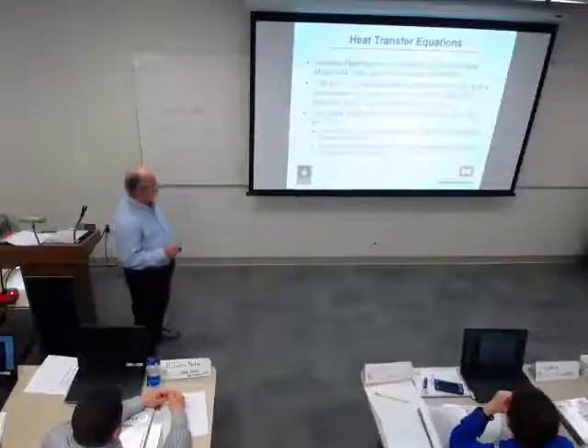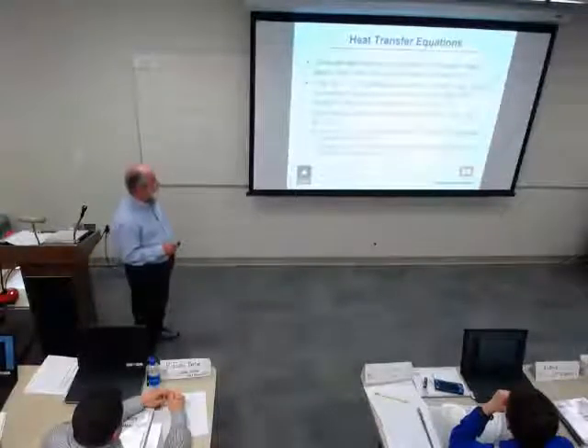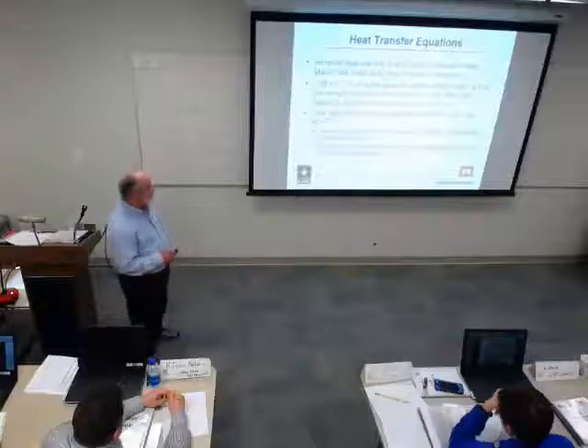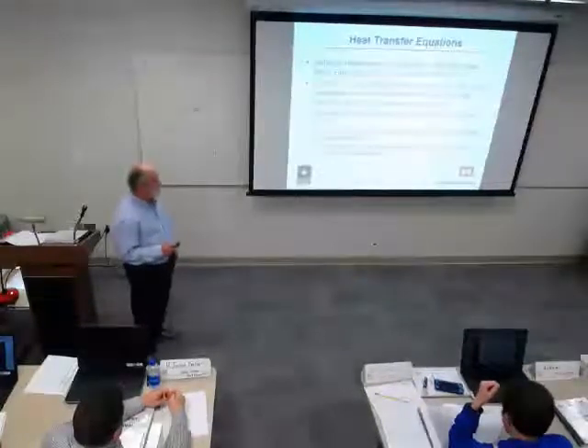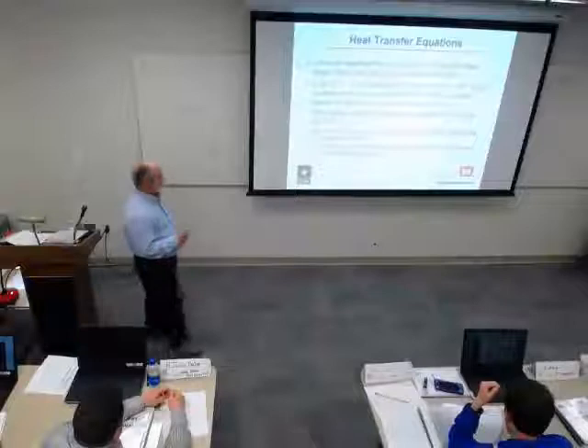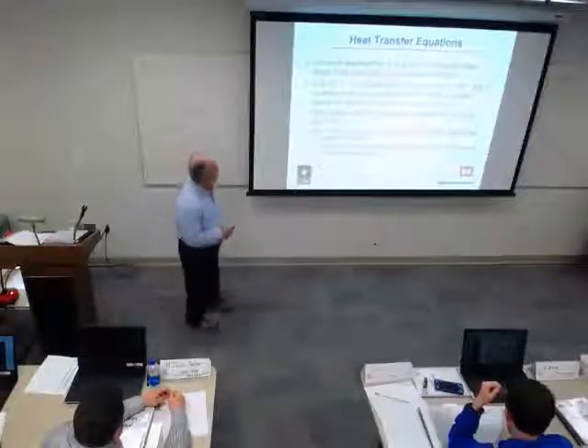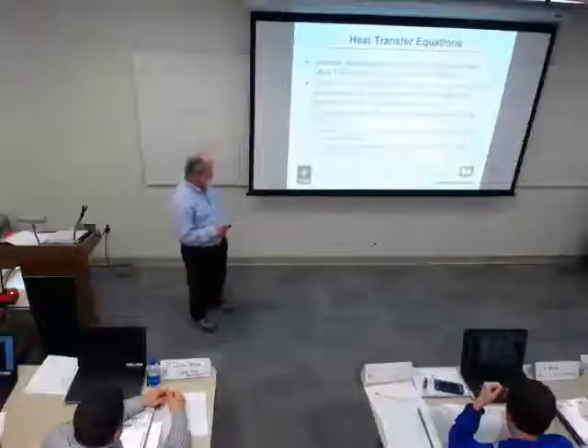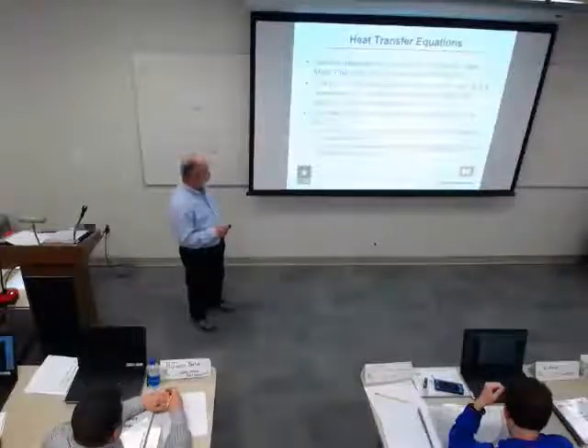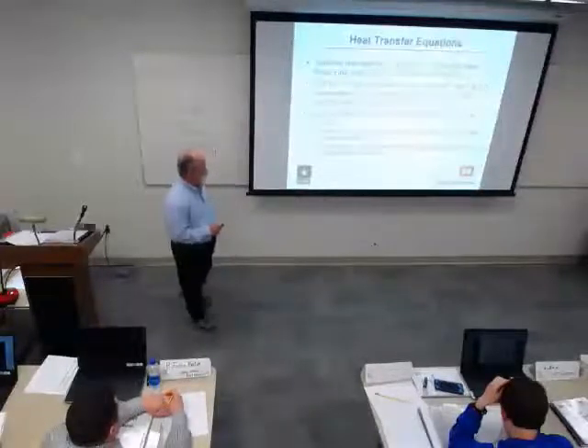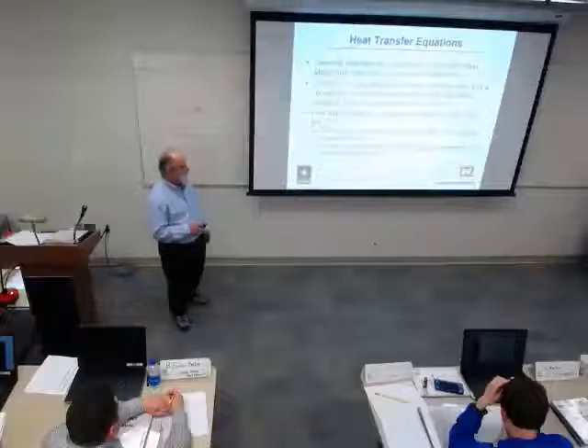And then the flow rates that are shown are standard conditions, 14.7 psi and 70 degrees Fahrenheit. Generally, this is good up to 1,100 feet. We're going to talk about that. ASHRAE is a little tighter than the TAB guys. And normally you ignore the temperature change and humidity changes with normal air system temperature ranges.